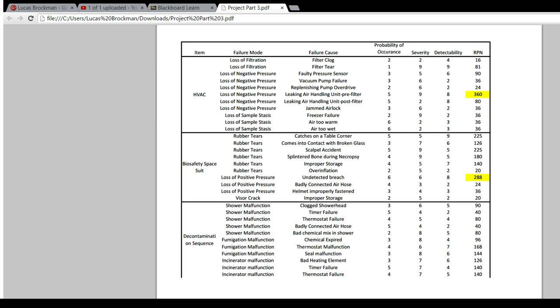The suits are operated under positive pressure for the exact opposite reason that the lab is operated under negative pressure. If there's some sort of breach in the suit, the air is blowing out so no microbes can get in, so it protects the personnel inside. But if this breach goes undetected for long enough, if it widens, if the hose is unplugged for any reason, like moving from room to room, then it's very possible for the positive pressure to be lost and for microbes to enter.